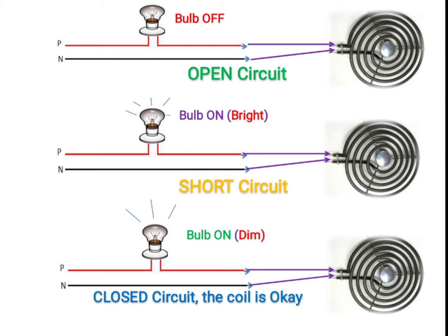Let's go ahead, but before that, let's recap. When we make the series lamp test and find the bulb is off, it means it's an open circuit. If the bulb is on but bright, as in the second diagram, it means a short circuit. And in the third case, if the bulb is on but dim, whether little dim or very dim, it depends upon the power consumption or dissipation in the coil. So if it's dim, that means it is a closed circuit and the coil is okay. I hope you understood this. Let's go to the next part.